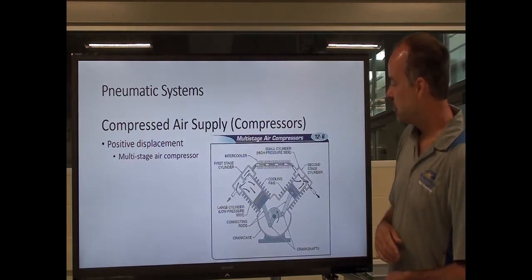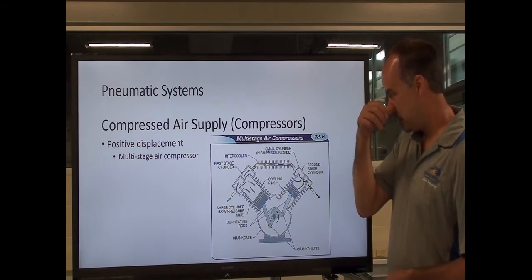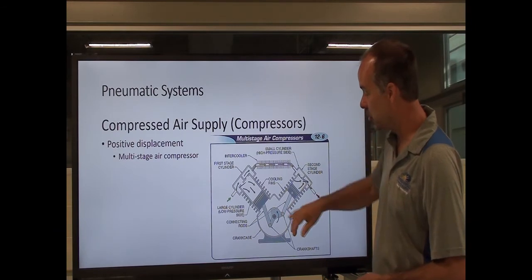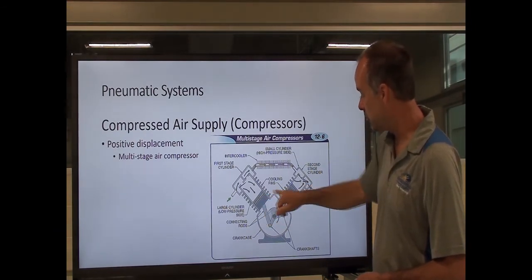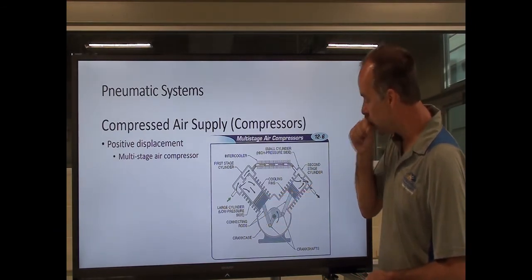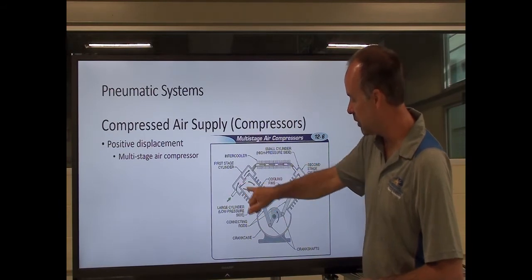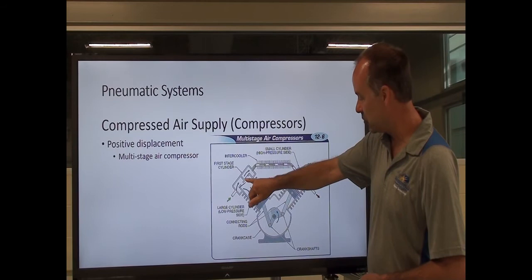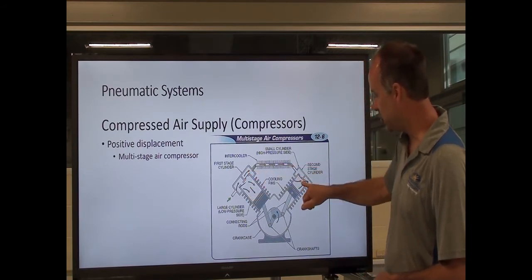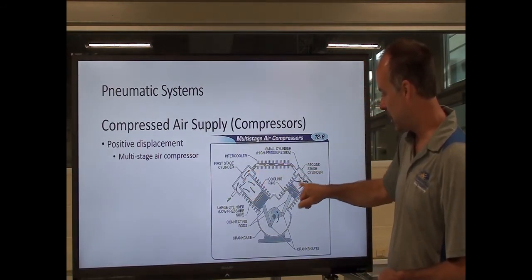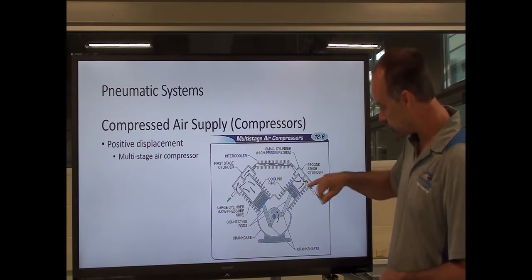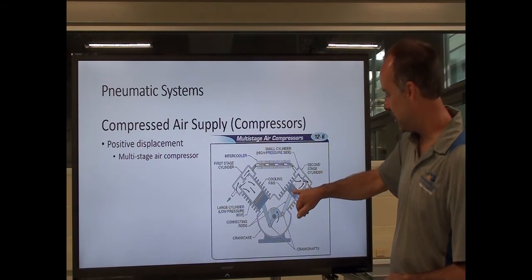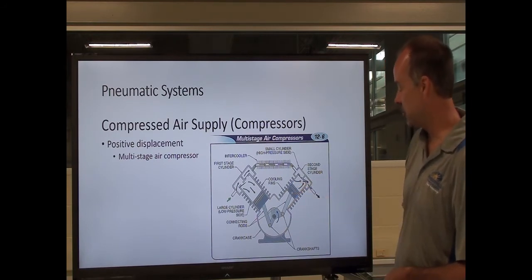Multi-stage air compressors are used in systems where you want to generate a lot of pressure. The way a multi-stage works is with multiple pistons: the first piston draws air in and compresses it, but the outlet of this first stage doesn't go to the receiver — it goes to another piston, which multiplies the air pressure. It pulls the air in at an already compressed state, then compresses it more and sends it out to the receiver.